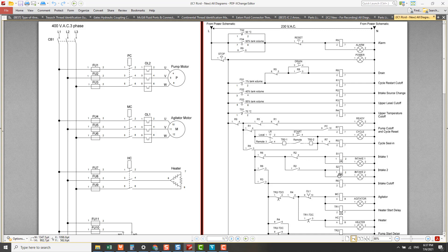Now I check the earth fault at the load. I normalize the wiring back to S2-2 and Intake 2-2, then open S2-1 and Intake 2-1. If the resistance is open circuit, there is no earth fault before the load or at the load. If there is a resistance reading, the fault is confirmed at the load — whether at the S2 solenoid valve or the Intake 2 load.